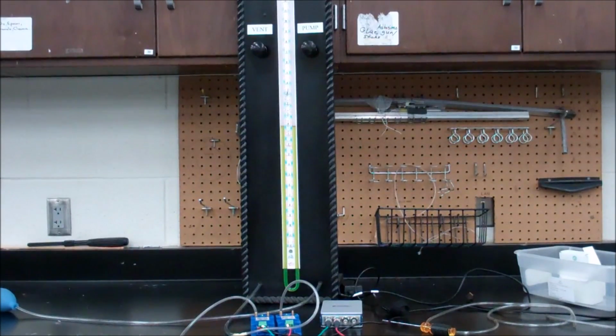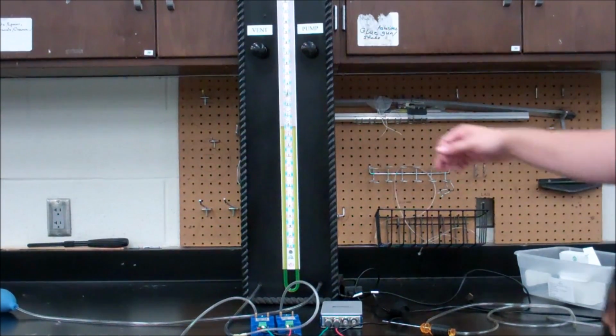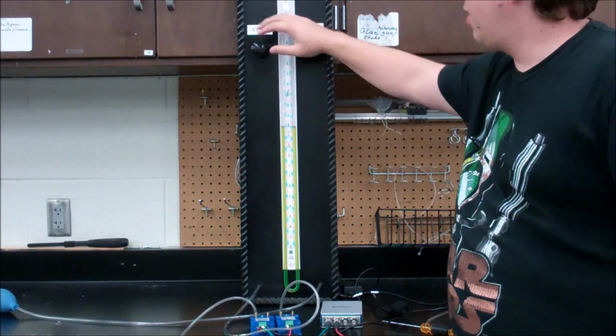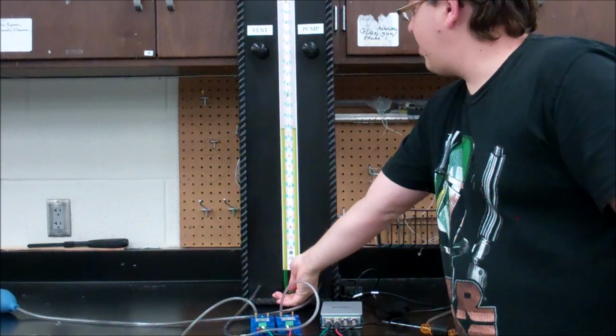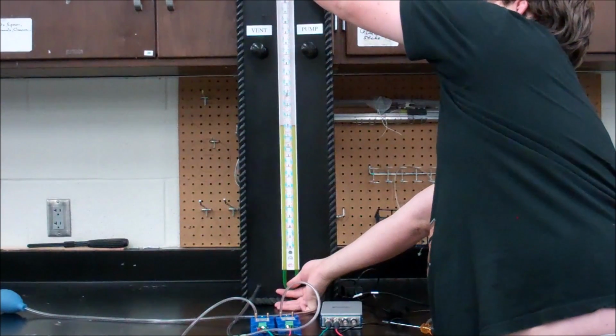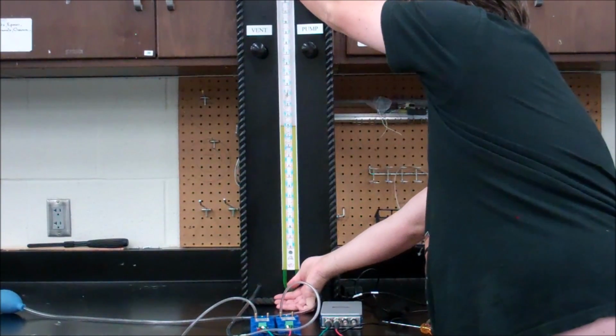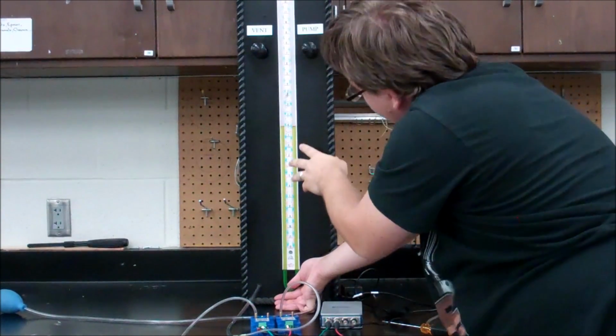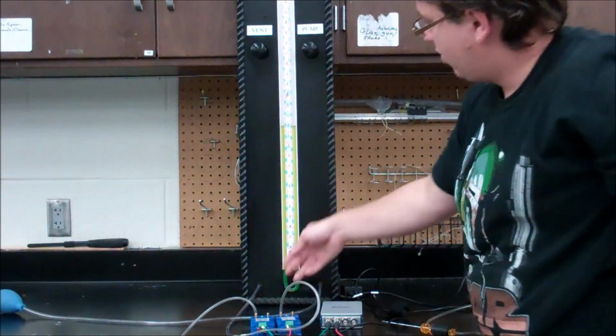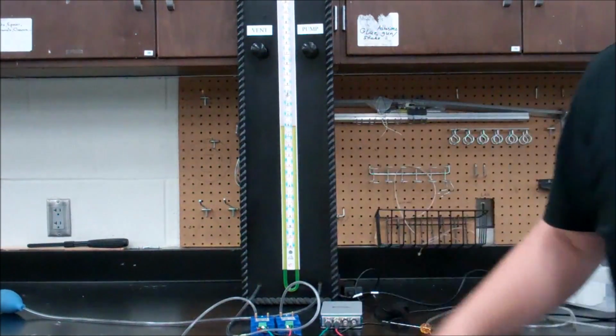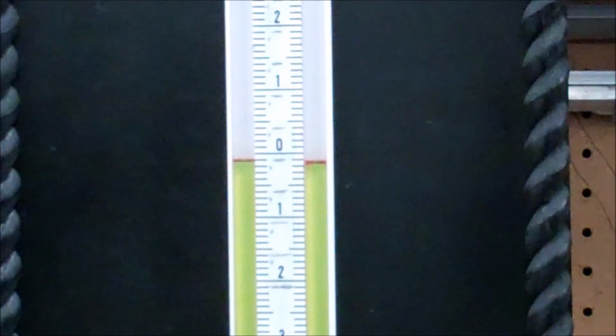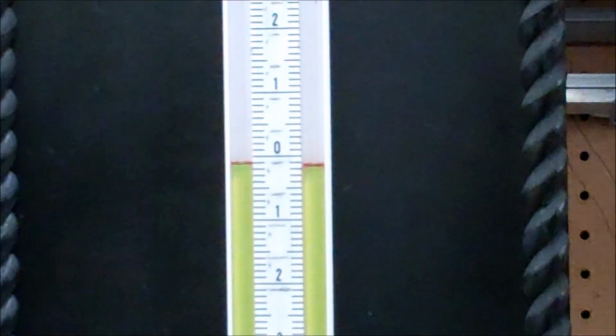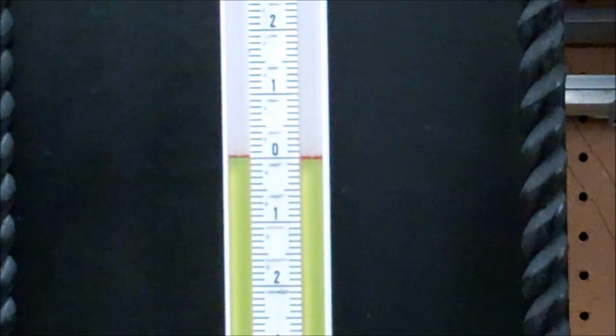So now that both of the pressure transducers are hooked up, we're going to learn how to use the manometer. Now you notice that you can slide this a little bit up and down. What you're going to want to do is make sure that you get the water level around the zero. Now if it's off a little bit, say like this, what you can do is push the whole entire tubing up and down to get it to zero.